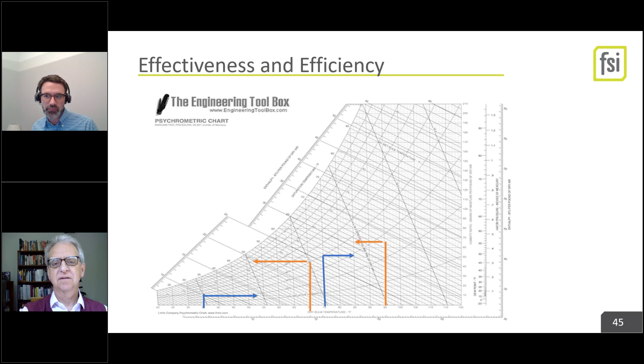So this code updates the requirement from 60% heat recovery to 68% heat recovery, and updates from 50% energy recovery to 60% energy recovery for Washington State, and Seattle already had 60% energy recovery. So this is the energy recovery version, and it works on enthalpy over here on the left. So your total energy recovery at 60% can be rather more advantageous than your heat recovery at 68%. Even though it's 8% more, your heat recovery can, in total, do less for enthalpy for you, for the total energy recovered. So that's why you get different thresholds for sensible versus for energy versus heat recovery.